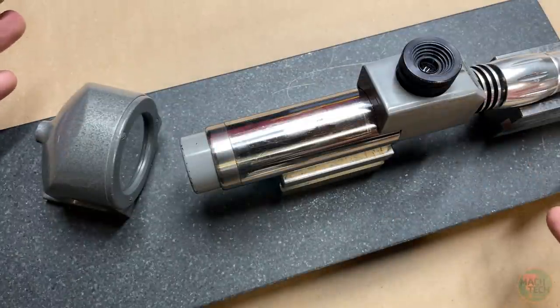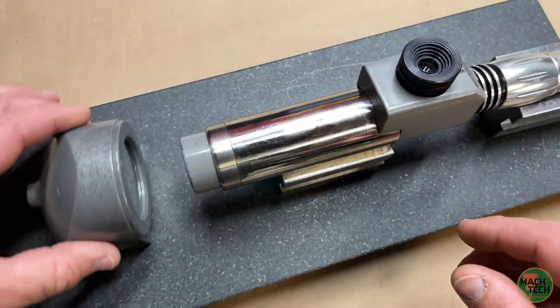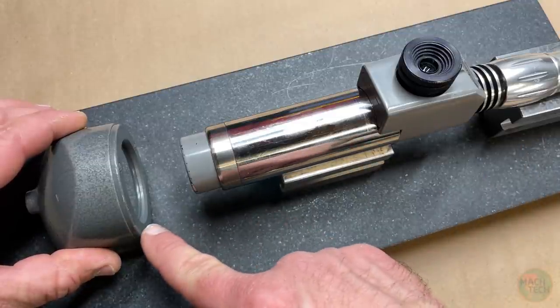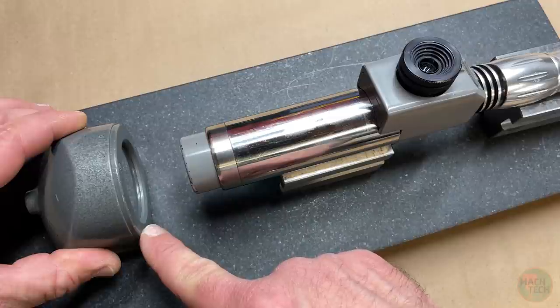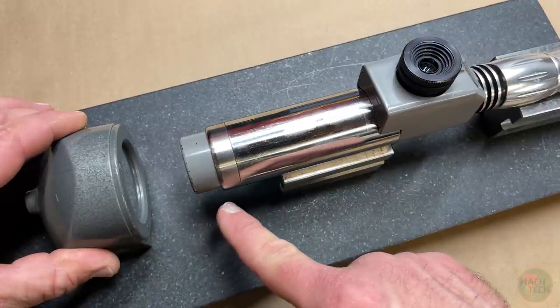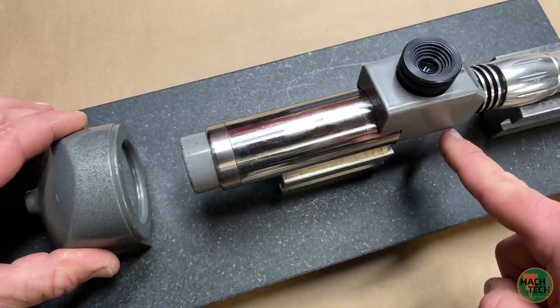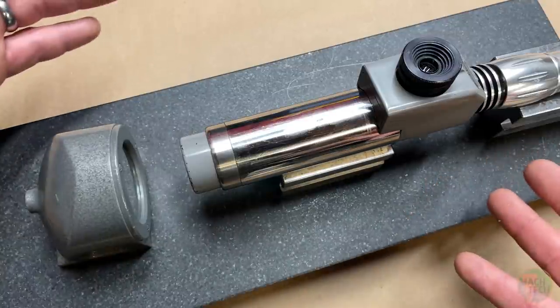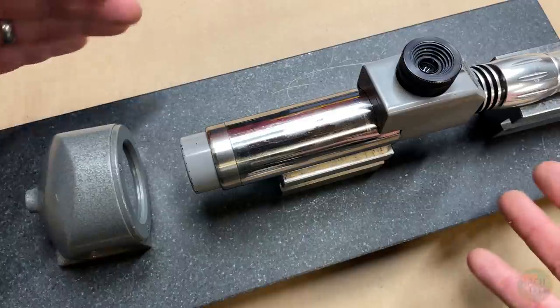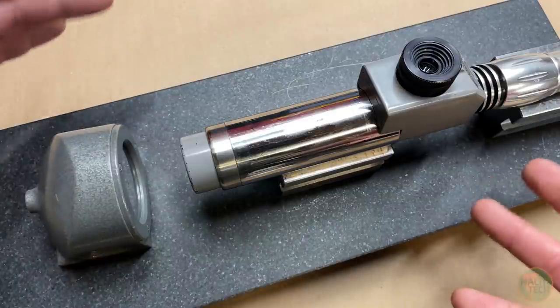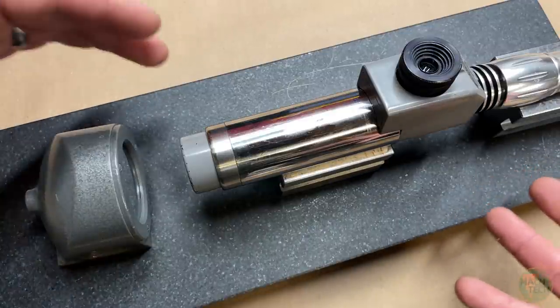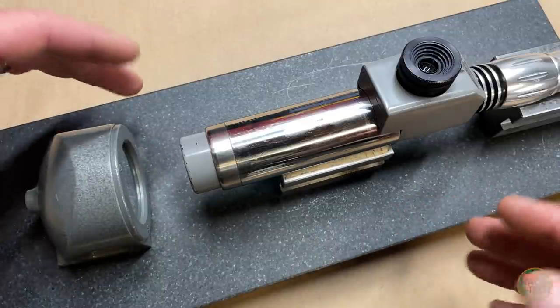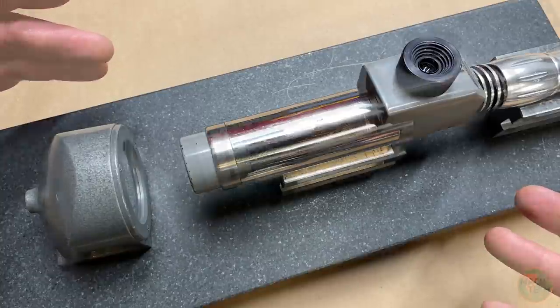So what can we do with this? Well, if we place a mirror in the optical path some distance from the auto collimator, then the image of the crosshair will be reflected off the surface of the mirror and it will re-enter the lens and get refocused at the focal point. This is actually where auto collimators get their name. They are optical instruments, basically telescopes, which are auto or self collimating. The optical system creates and projects a collimated beam of light and then reflects and refocuses the beam back into itself.